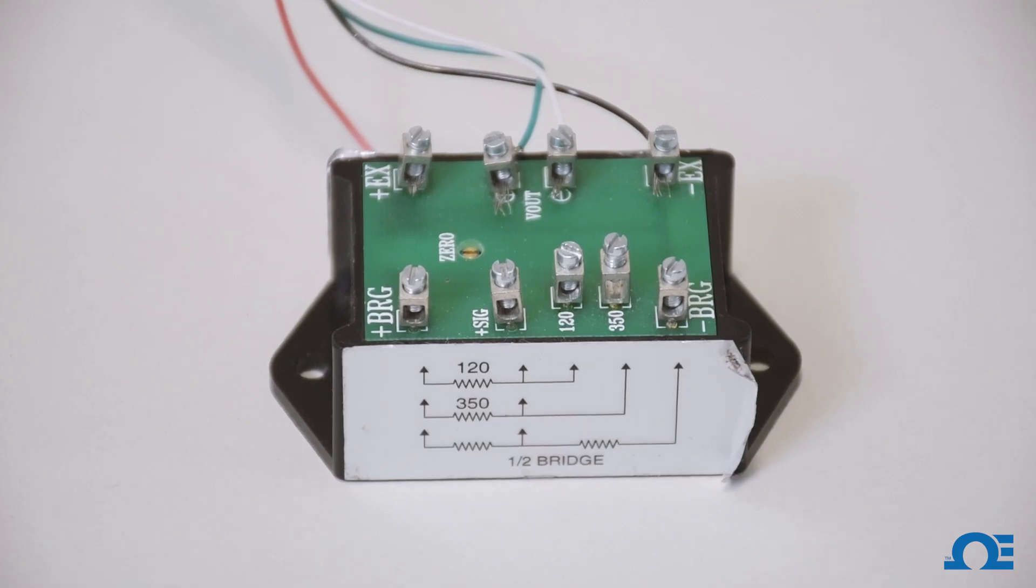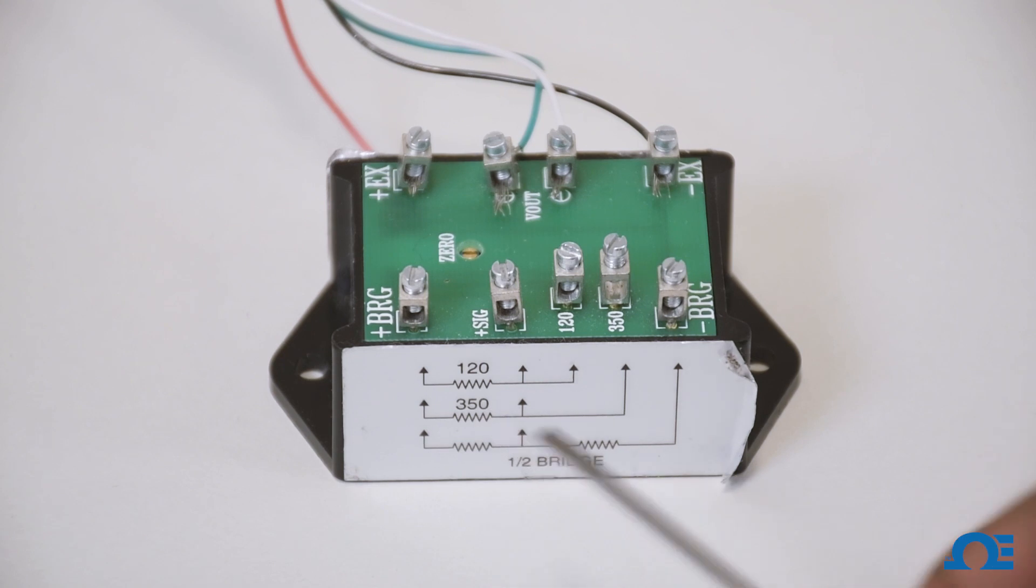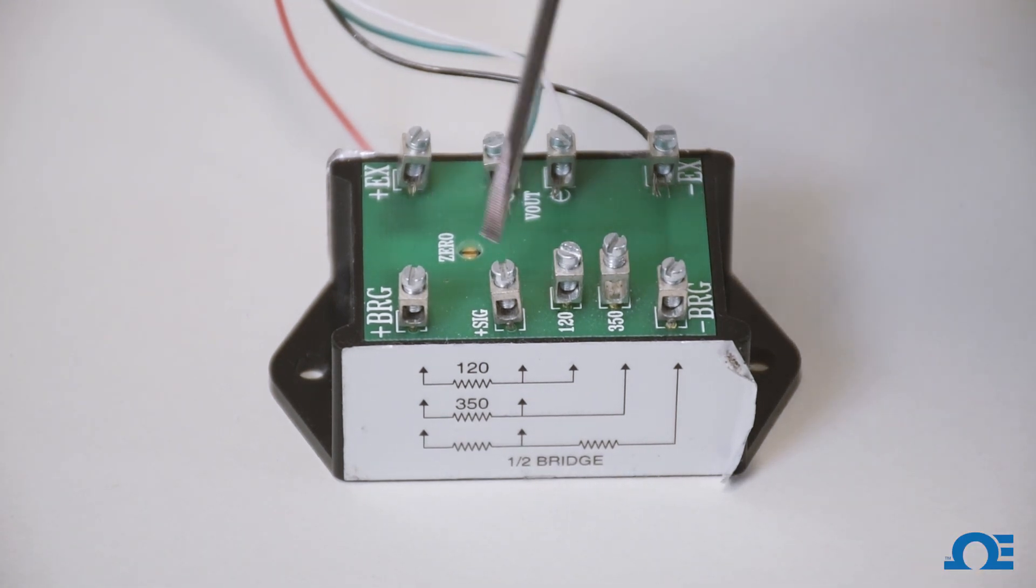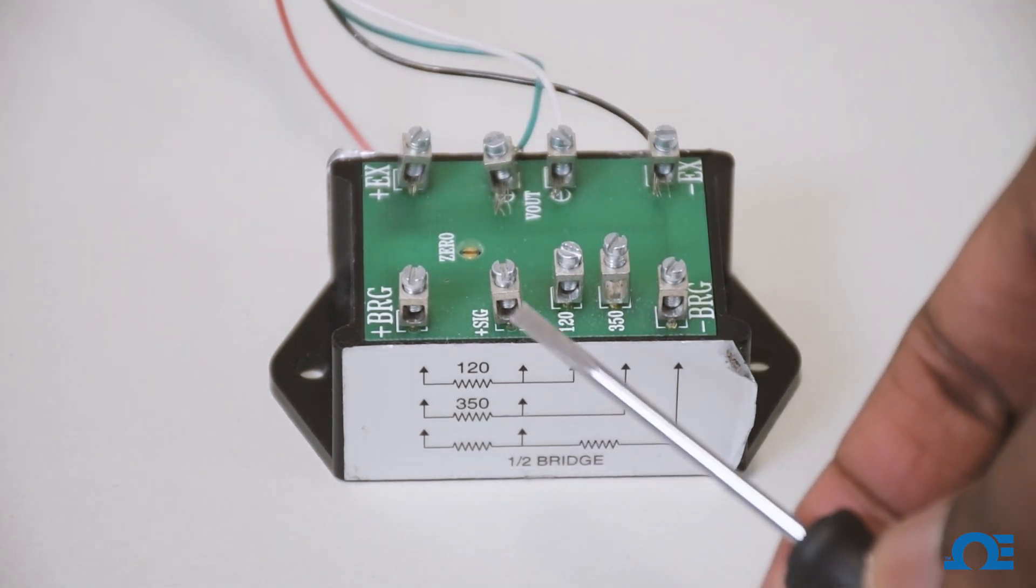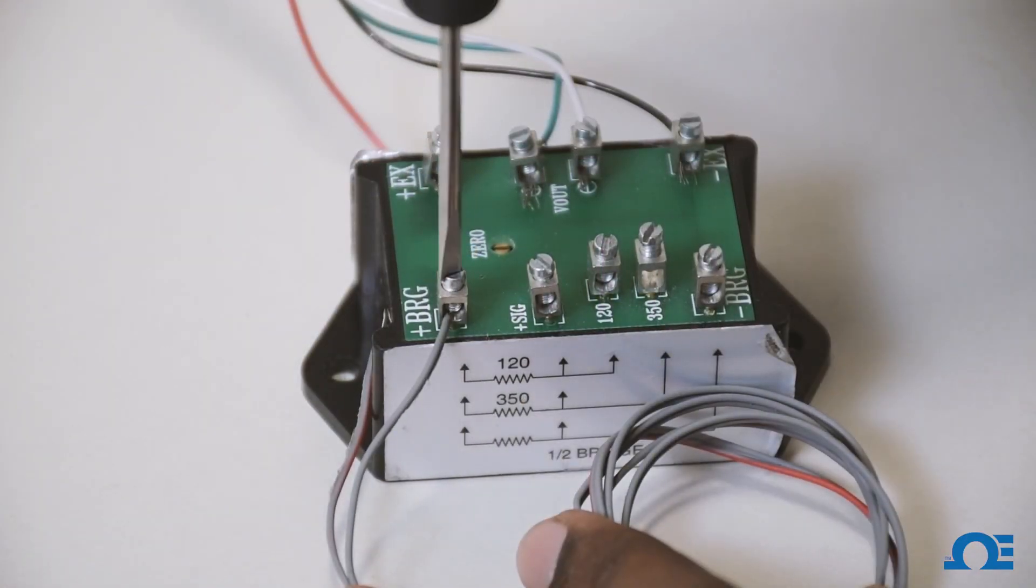If you look at the side of the BCM, you'll see a schematic showing how to connect your strain gauge to the BCM-1 module. There is a 120 ohm strain gauge connected to plus BRG and plus signal, and there is a jumper between plus signal and 120. Let's go ahead and wire it.